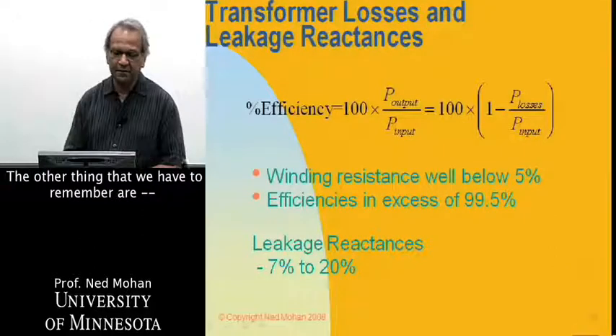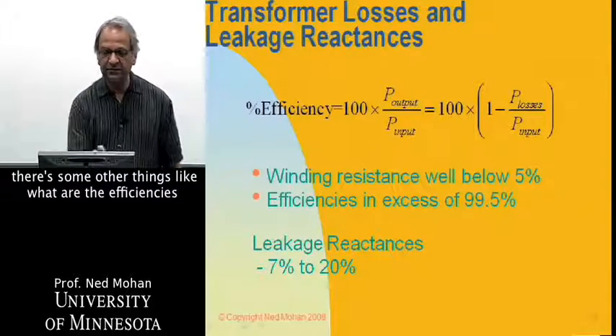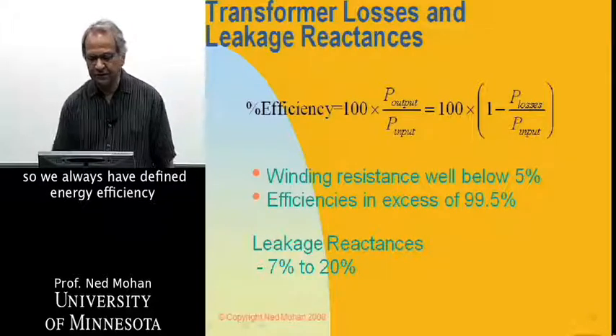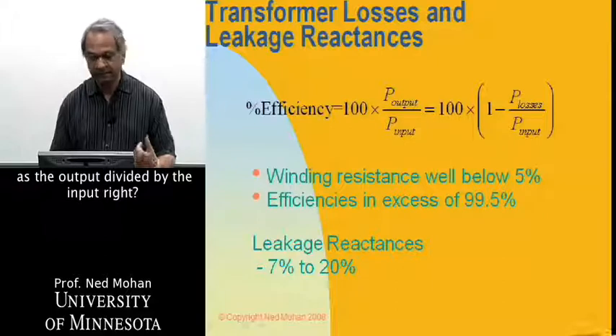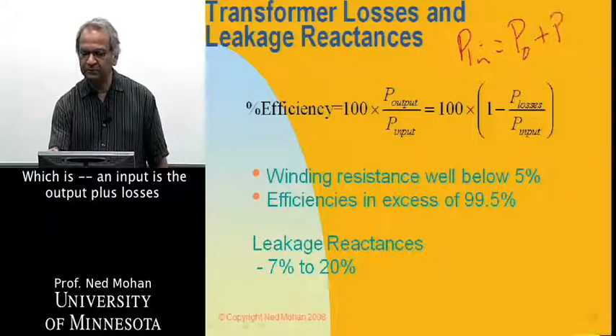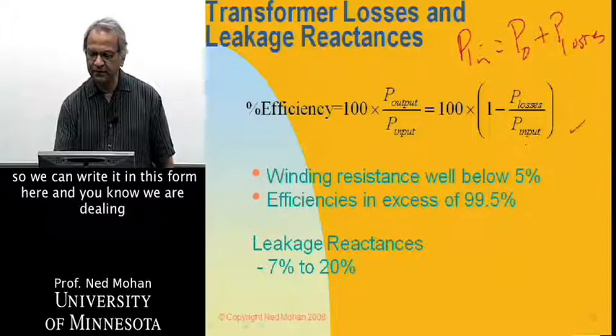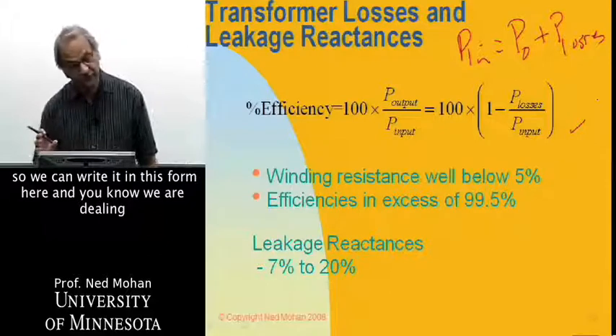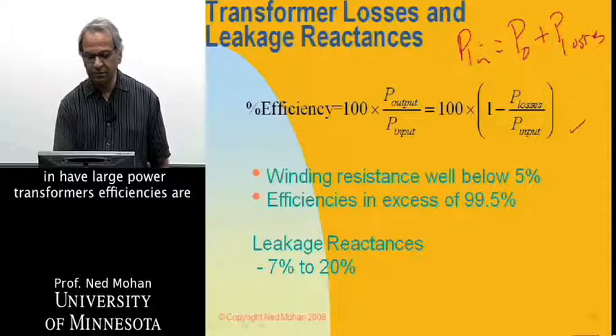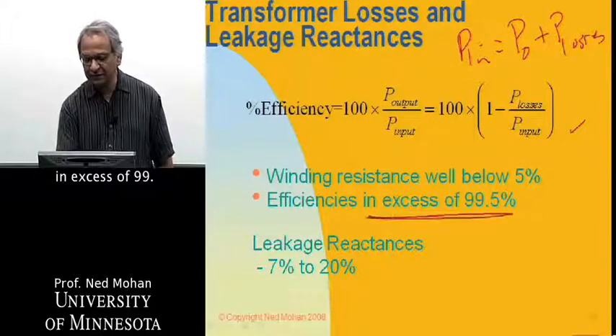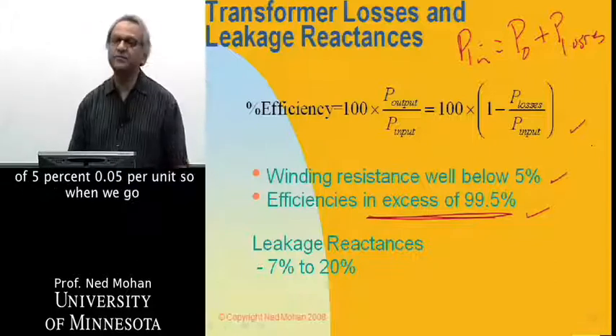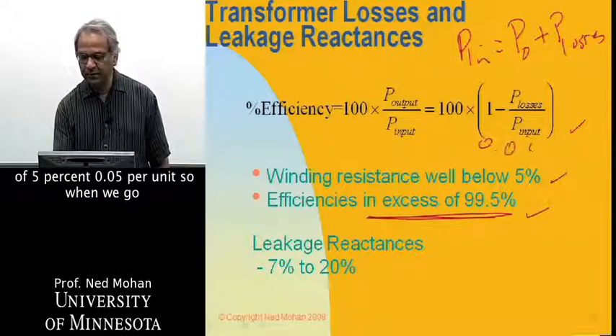The other thing we have to remember are, there's some other things, like, what are the efficiencies of these transformers? So, we always have defined the energy efficiency as the output divided by the input, right? Which is, an input is the output plus losses. So, we can write it in this form here, and we are dealing with extremely high power here, so efficiencies have to be very high, and they are. In large power transformers, efficiencies are in excess of 99.5%. And winding resistances are well below 5%, or 0.05 per unit.